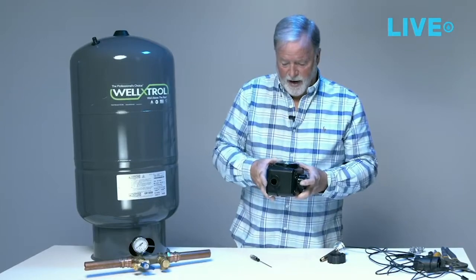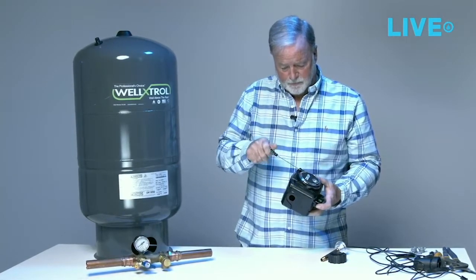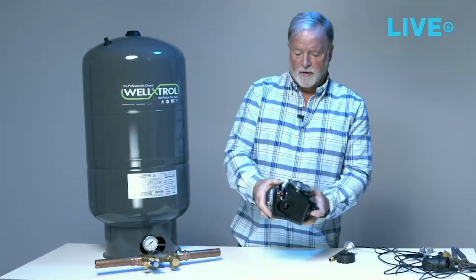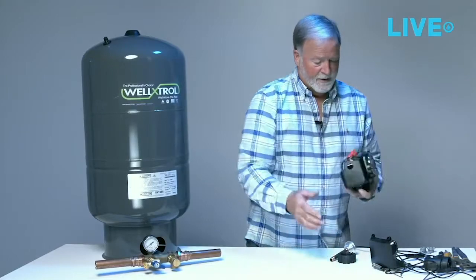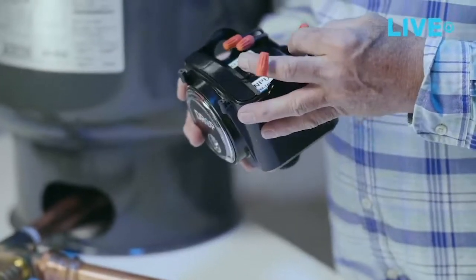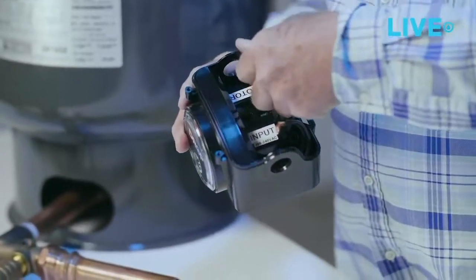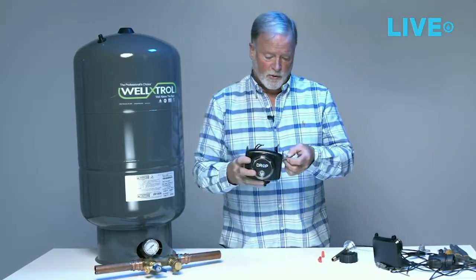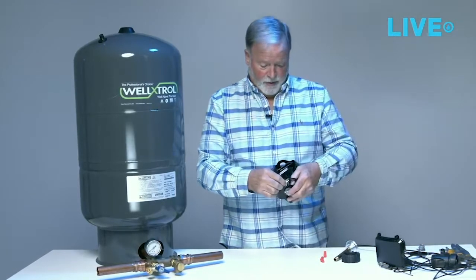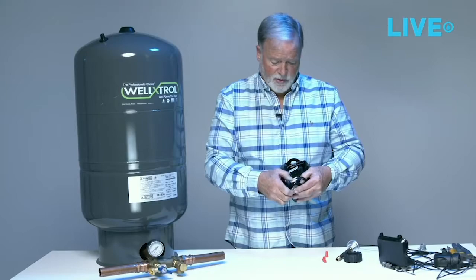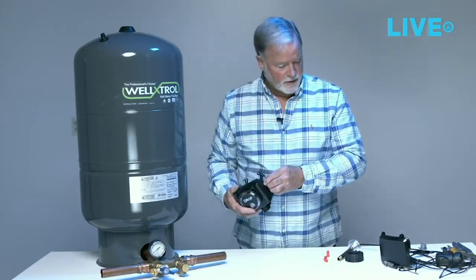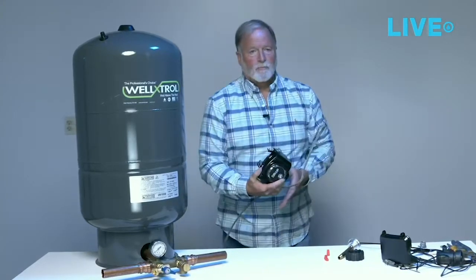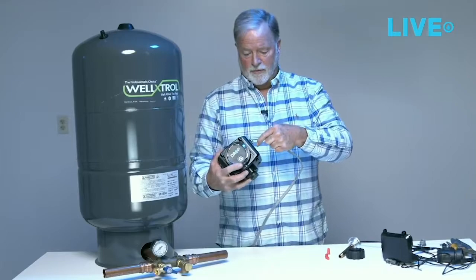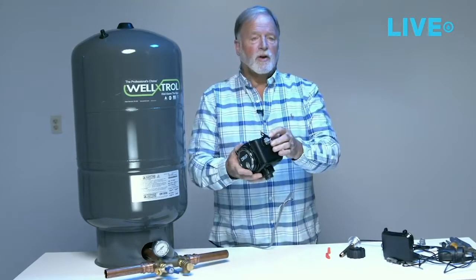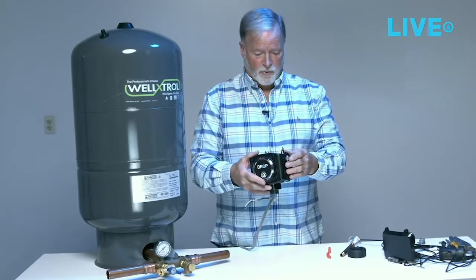The next thing we do when you pull it out of the box is you take the cover off, and the cover is 2 screws, and then it unlatches off the back, and you'll see the wire tails as we talked earlier, and the wire tails then are just at a standard length so that you can put a pre-knocked out hole. So you put a connector in there for whatever your wiring means is, whether it's conduit, NM, UL, whatever. You would put your connector in, and then you feed your wire. Obviously, you feed your wire through that connector. The point is, you don't have to drill any holes. You don't have to do a knockout. The connectors are already there.